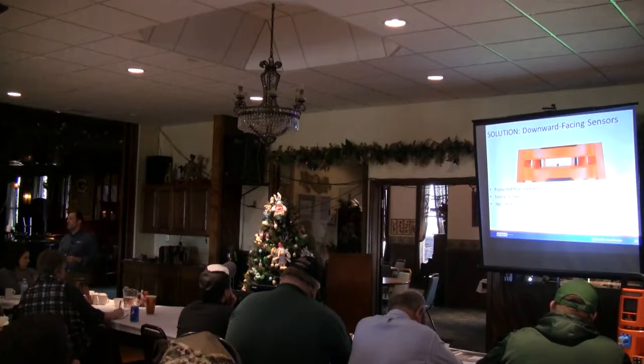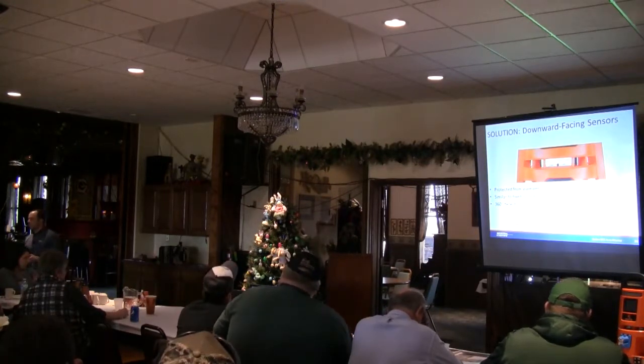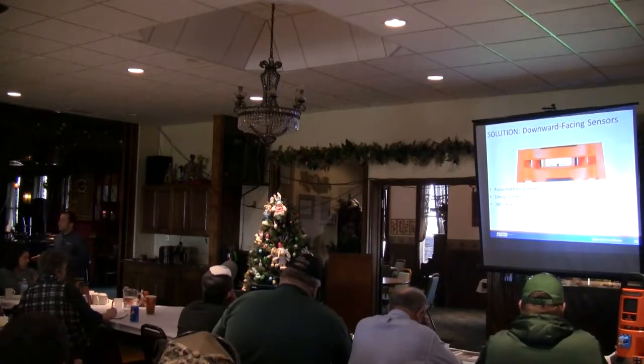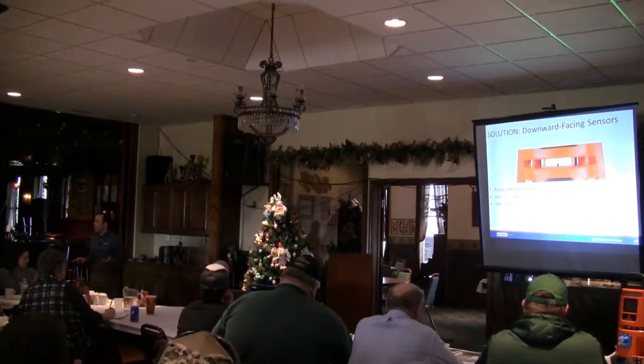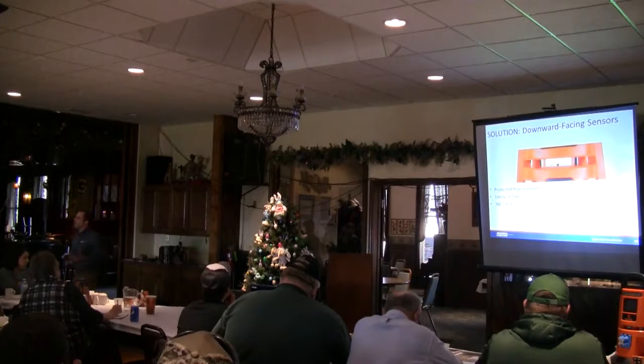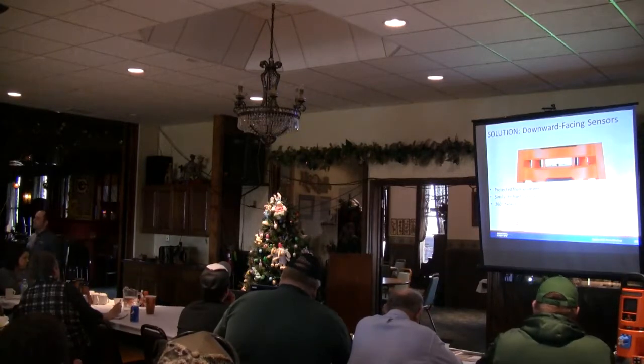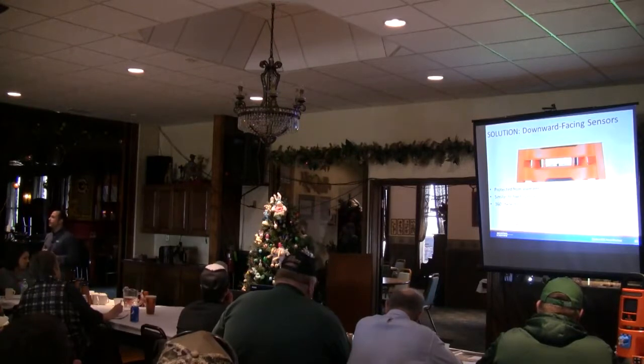So I'm not telling you to stay in gases above 20 ppm. I'm saying that you could set this to 9 or 8 or 10 and be able to silence it. But if it ever creeps above 20, the instrument will go into alarm and won't come back out until you get below that alarm threshold. Yeah.